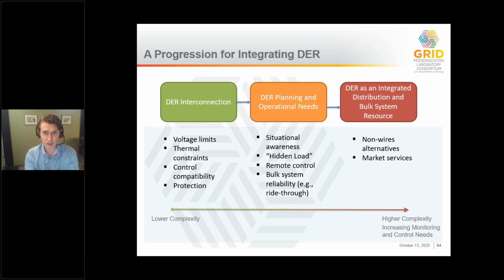Interconnections typically don't look at contingency configurations, so switching scenarios, like we'll look at later in an example, aren't really accounted for. A next step is to think about how to integrate DER more broadly into planning and operational frameworks—contingency operations, understanding what amount of load is hidden by DER contributing energy to the grid, and larger system issues like ride-through.